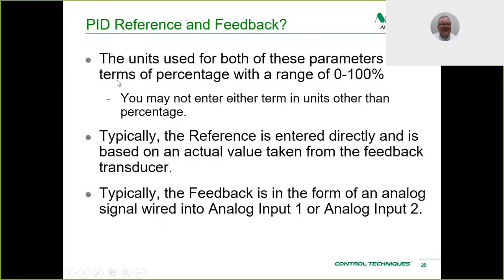Now the reference and the feedback, here's something else. The units that we are expecting you to enter for the reference and feedback are in terms of percentage, with a range of 0 to 100%. You cannot enter either term in units other than percentage. So we've had people want to enter the set point in pounds of tension, the set point in gallons per minute, and things like that. You can't do that directly in menu 14.